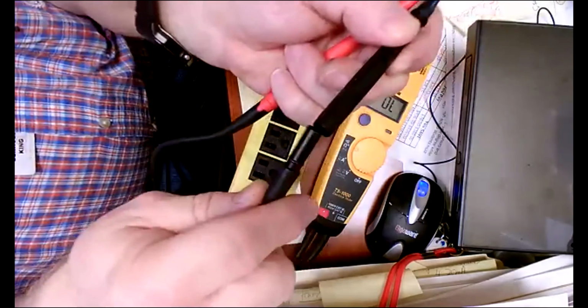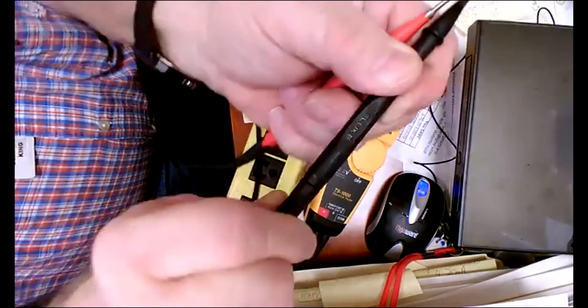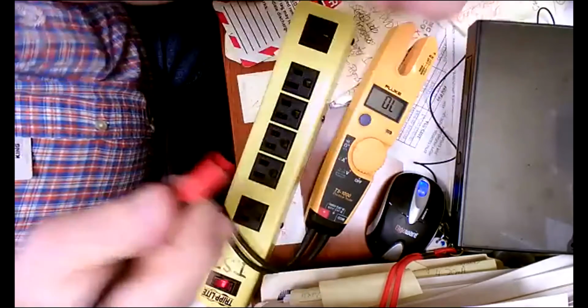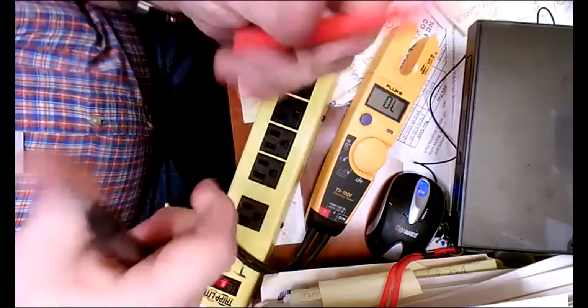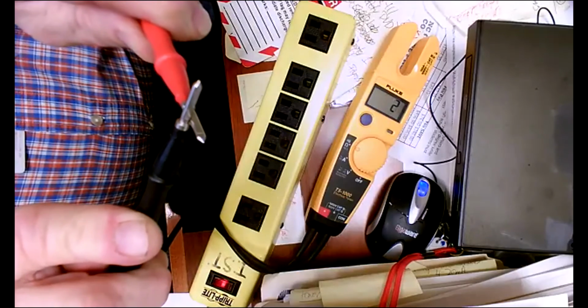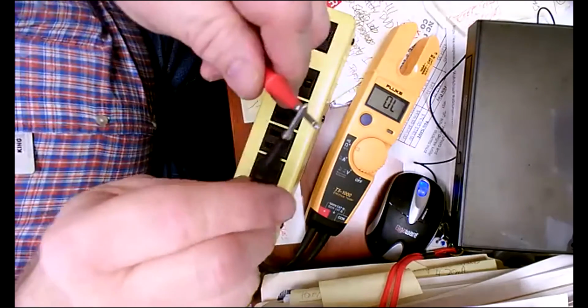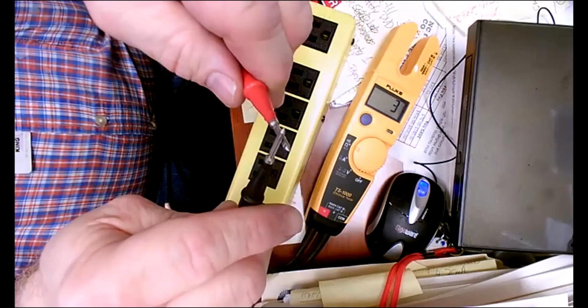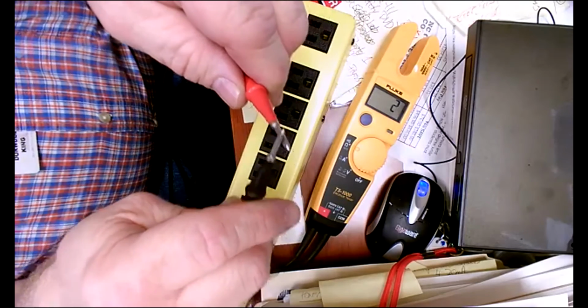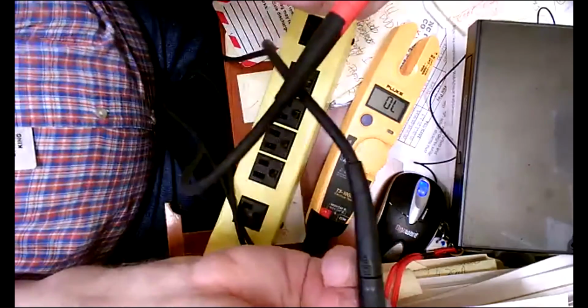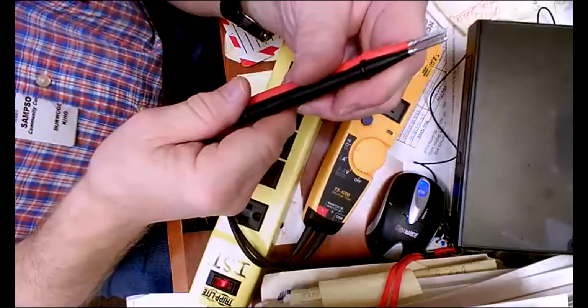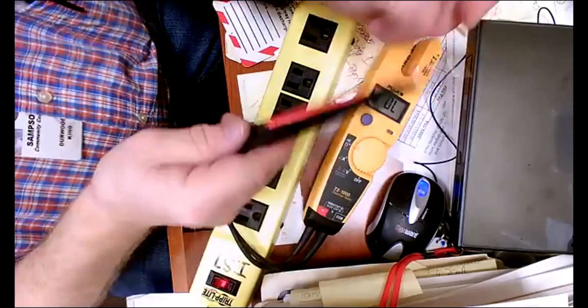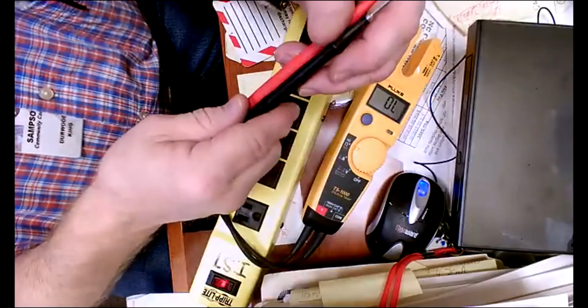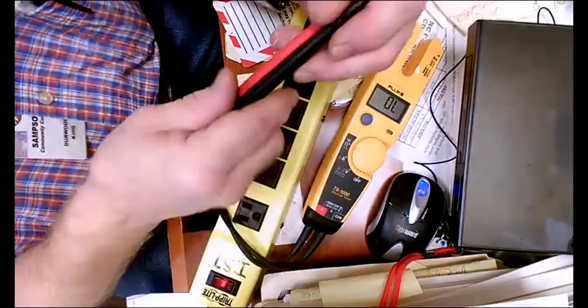Now here, you've got quick connects that can be an issue. So if you take the quick connect apart, I don't particularly like these. But you do that and you want to reseat it and take that out and reseat that again and try it again. So you have 2 ohms of resistance in these test leads. It's better if it's actually below 1, but there is a little bit of resistance in there. And what that can do is throw accuracy off a small amount, not a lot, but a little amount.